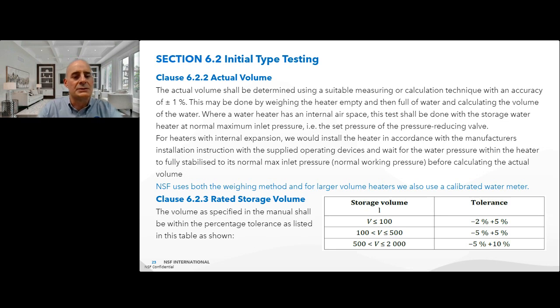Clause 6.2.3 is the rated storage volume. So the volumes as specified in the manual should be within the percentage tolerances as listed in the table as shown. So as I said, you're allowed a tolerance on your actual water volumes, and that's got to be within that tolerance band shown in the table.